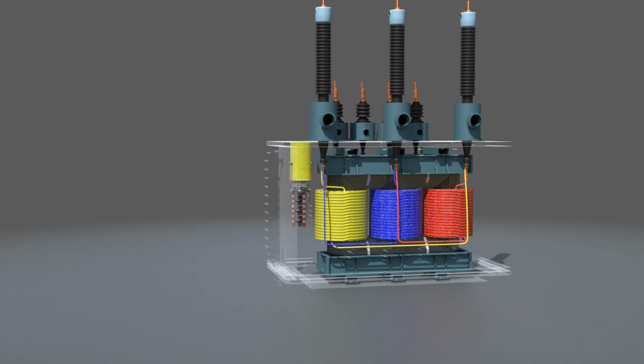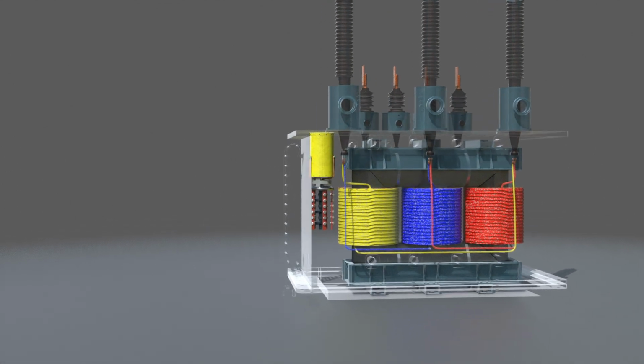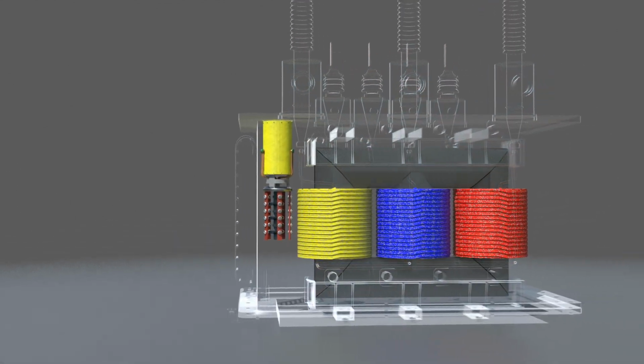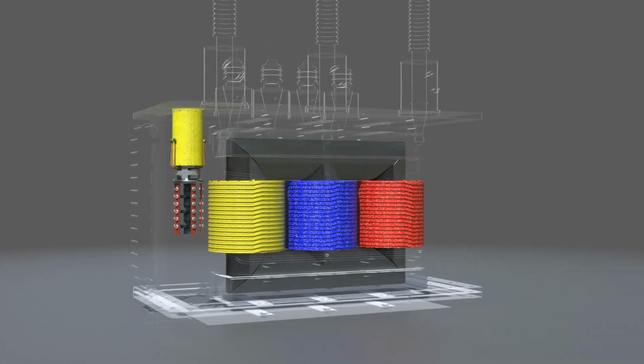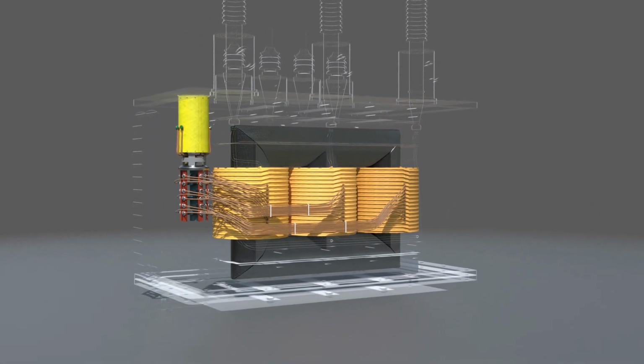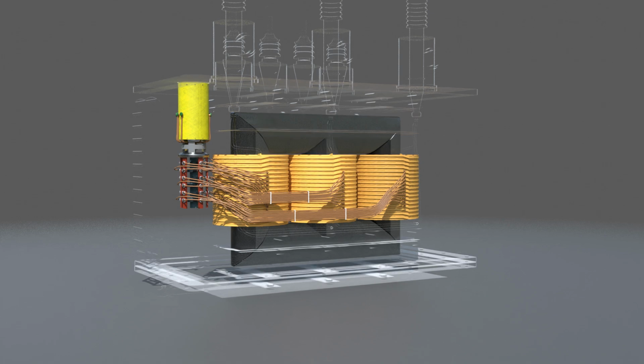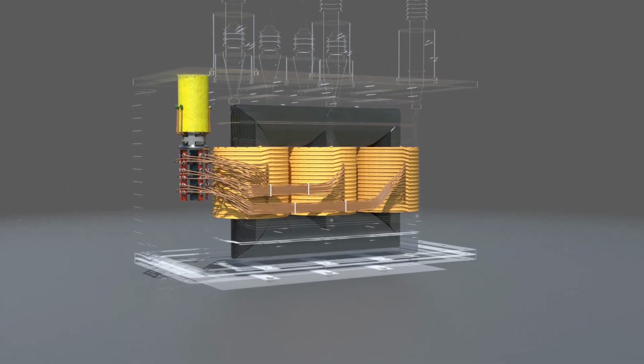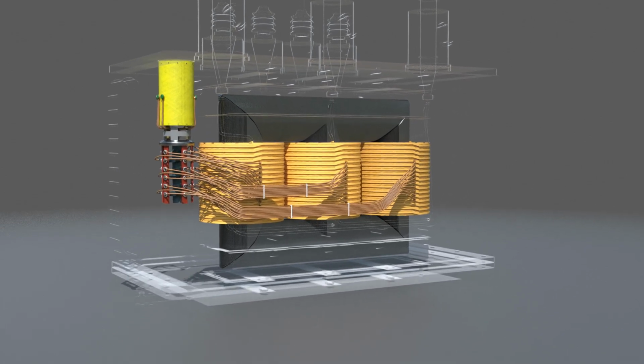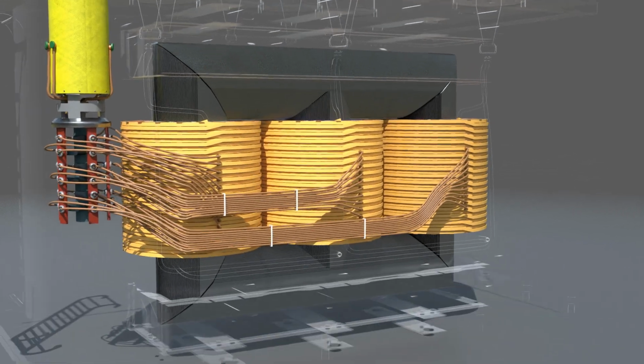Voltage in a power grid is not constant. It shifts with demand, supply, or network changes. To maintain a constant and stable voltage in transformers, tap positions are used. A tap changer modifies the number of turns in the transformer's winding, adjusting the voltage as needed.